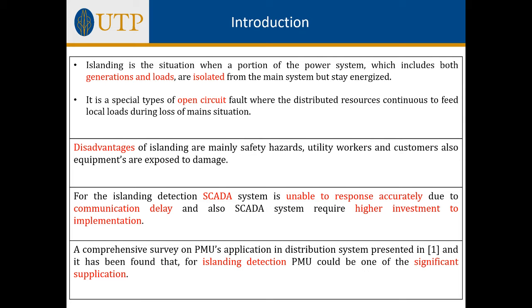So the introduction is that islanding is a situation when a portion of the power system, which basically includes the generation and the loads, is isolated from the main system but stays energized. So basically it's a special type of open circuit fault where the distributed resources continue to feed the local loads during the loss of mains. The main disadvantages of islanding are mainly safety hazards to utility workers and customers. Also, equipment is exposed to damage.